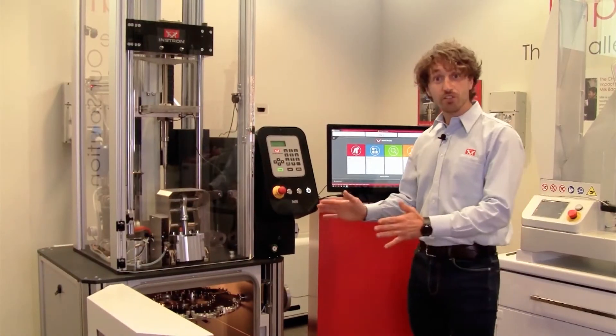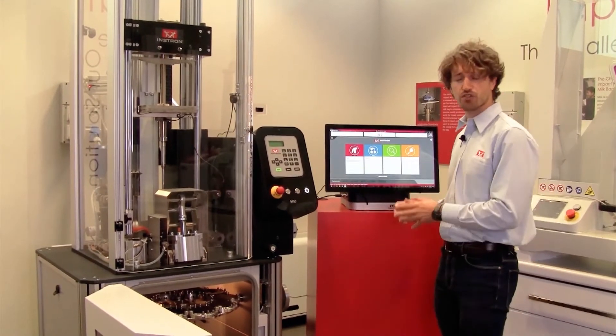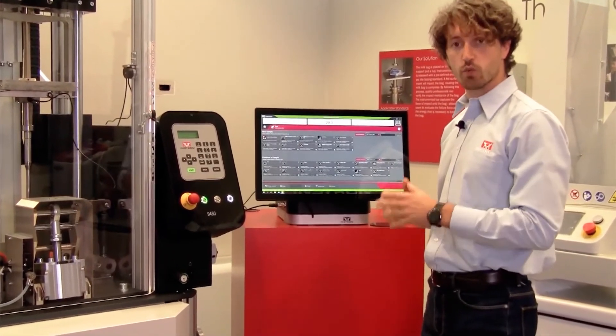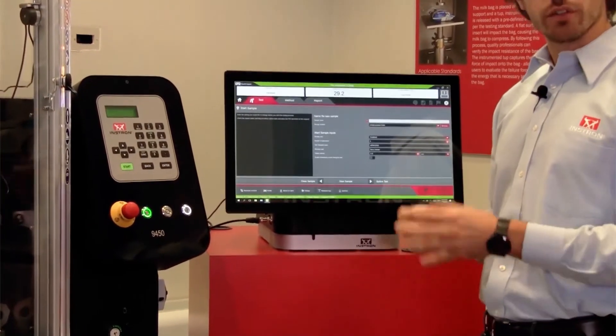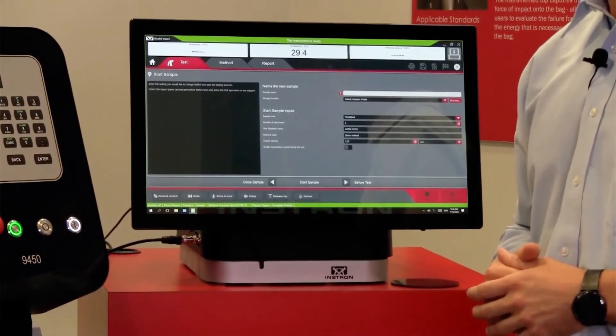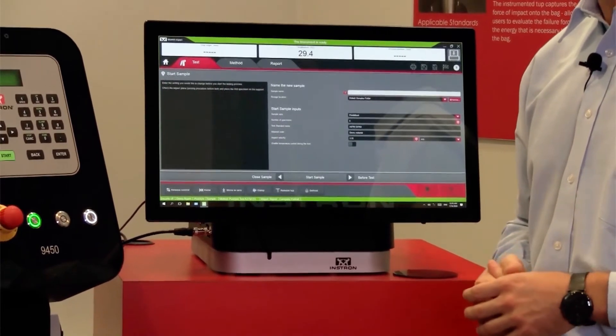Now that some key elements of the drop tower have been shown, let's see a complete test cycle. Once all specimens are correctly positioned on the carousel system, we approach the touchscreen controller with Bluehill Impact software. Opening the test area, we can select and customize a predefined testing method. Thanks to a set of smart defaults, it's extremely easy to cover the most common impact testing scenarios — there is no need for specific software expertise or extensive training with Bluehill Impact.